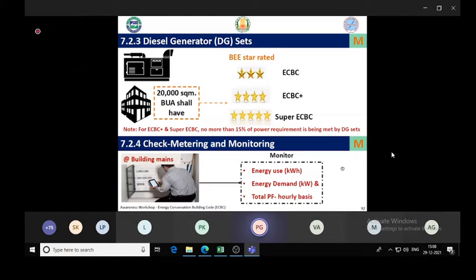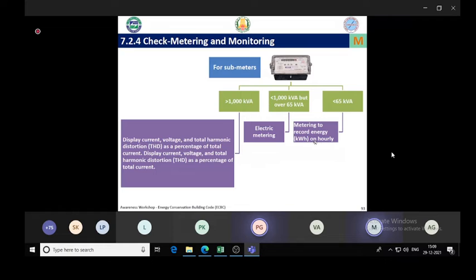Okay. Another mandatory point is the check metering provision. Apart from the meter provided by TANGEDCO, normally each building will have a billing meter provided by TANGEDCO. Apart from that, we need to provide our own internal meter to monitor our energy consumption. So this is mandatory. That meter should be an energy meter capable of measuring kWh. For a smaller building, only kWh. If it is a bigger building, we need to monitor other parameters like power factor, kW, kVA, and all that. And for larger buildings, we also need to monitor the harmonics. So a meter with such capability should be installed for internal metering purposes.